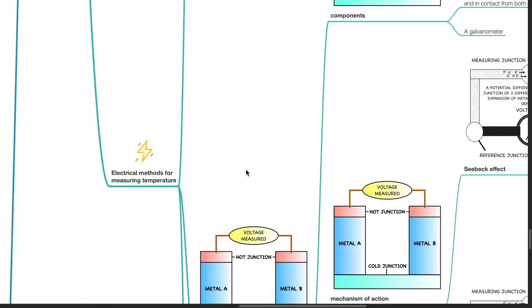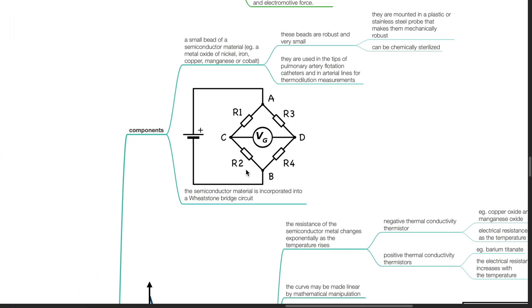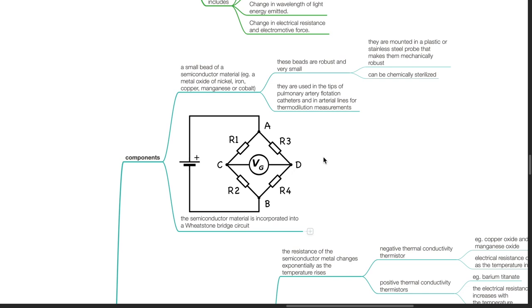Electrical methods for measuring temperature: the thermistor. A thermistor consists of a small bead of a semiconductor material such as a metal oxide of nickel, iron, copper, manganese, or cobalt. These beads are robust and very small. They are mounted in a plastic or stainless steel probe, making them mechanically robust and able to be chemically sterilized. Thermistors are used in the tips of pulmonary artery flotation catheters and in arterial lines for thermodilution measurements. This semiconductor material is incorporated into a Wheatstone bridge circuit.